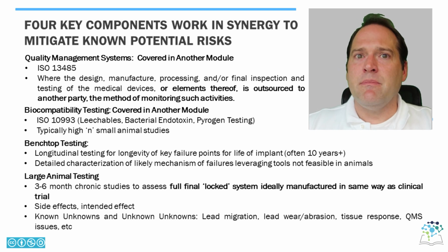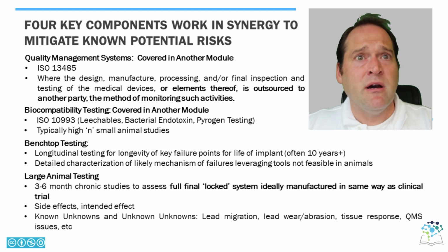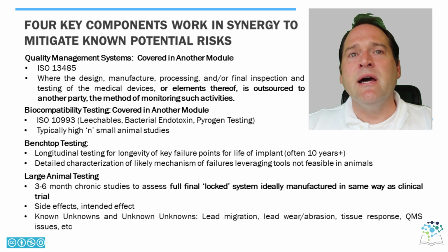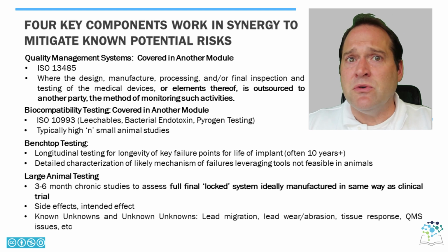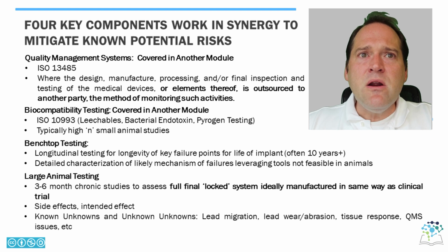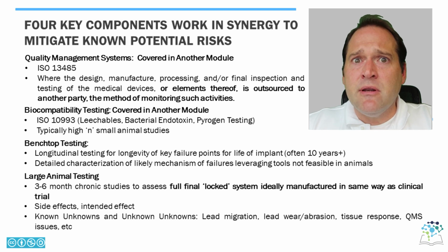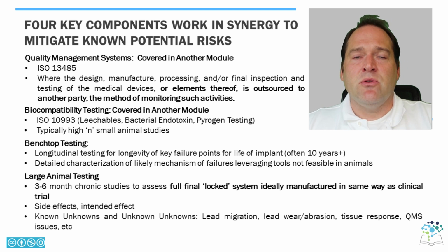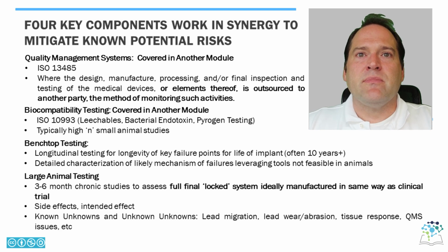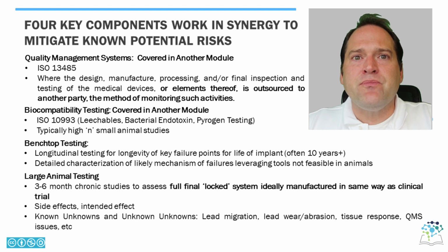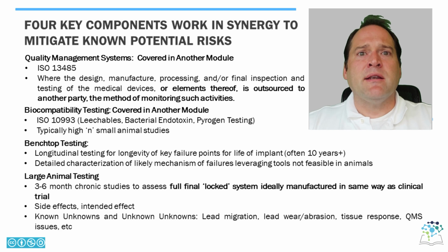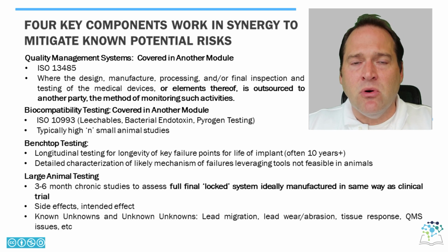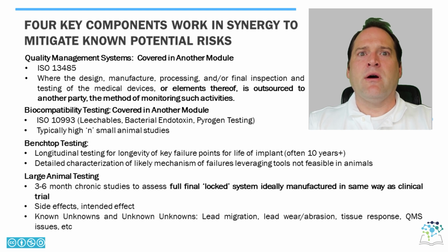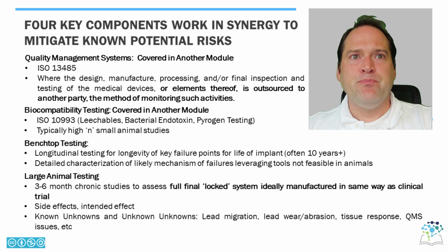The other thing you do in the benchtop that you don't do in the large animal studies, because you might not be able to, is detailed characterization of likely mechanism of failure, leveraging several tools that aren't feasible in animals. Then the large animal testing is typically your definitive sanity check. It's typically a 3 to 6 month study to assess the full final locked system, ideally manufactured in the same way or as close as possible as will be done in the clinical trial. And this is intended to assess how different components might interact as well. So you want to change as little as possible between your GLP definitive chronic animal study and the actual IDE.